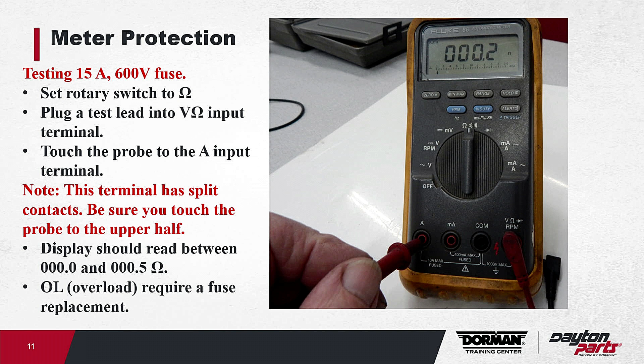But I ran out of them. You can test these though - here's an example with a Fluke. Set the rotary switch to ohms, plug the test lead into your volt ohms input terminal, and touch the probe to the A input. Don't forget those terminals have a split contact, so make sure you touch the probe to the upper half. There's your display - if it shows OL, you've got a problem. You can do the same thing on the 1 amp portion, the smaller one.